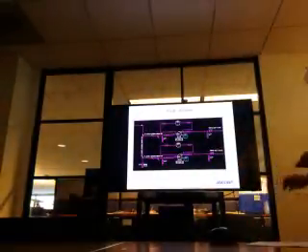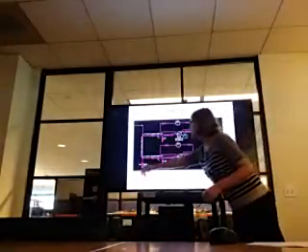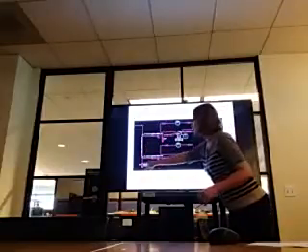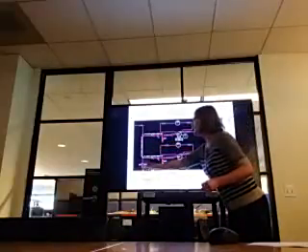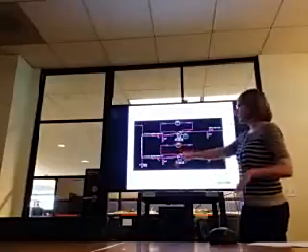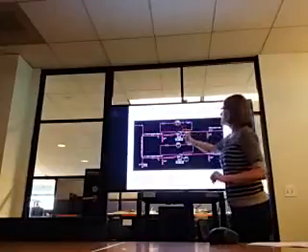Okay, so here's a P&ID example. And we talked about block valves. Block valves are isolation valves. You're just stopping the flow. So here we have a ball valve, 3/4 inch size. It's appropriate for this BBG01, just like we talked about. It's a drain valve, so they have a nipple here and a cap. They only open it when they want to take the cap off and drain the system. Here's a butterfly valve on a 3-inch line, perfectly appropriate because it's 3-inch and larger. We want to have butterfly valves. Here we have block valves around a piece of instrument in case they need to service that instrument.